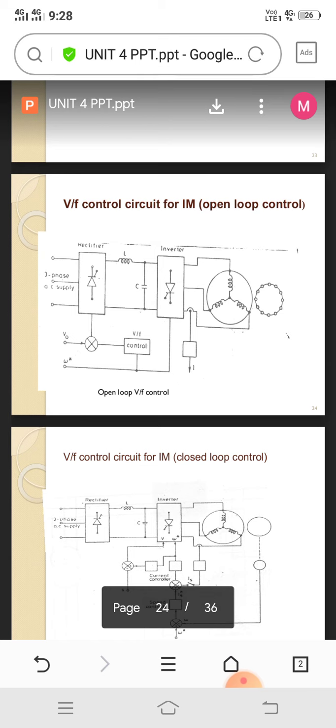A rectifier receives the three-phase AC supply with the relevant magnitude. This represented magnitude will reach the rectifier, after which the rectifier circuit gets the firing pulses. The rectifier also has 6 SCRs, each phase consisting of 2 SCRs. So 3 phases have 6 SCRs, 3 positive SCRs and 3 negative SCRs.